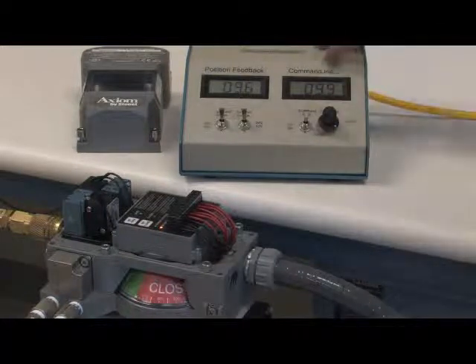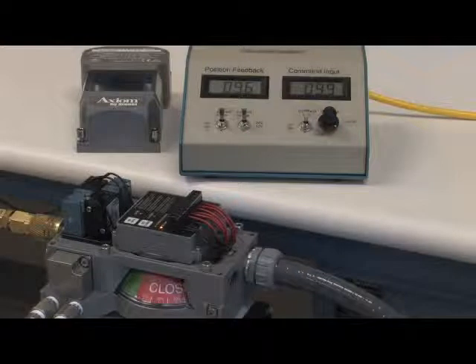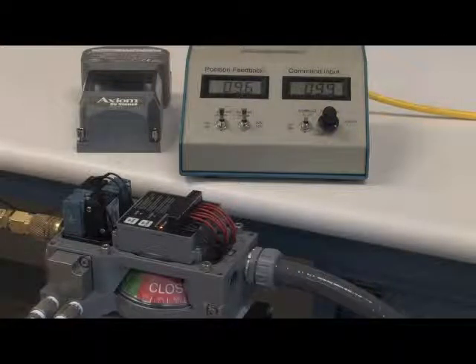Now, we'll close a little further. And you can see the input and the feedback are within the tolerable range of plus or minus 3 degrees, or plus or minus 4 percent of the milliamp full-scale reading.